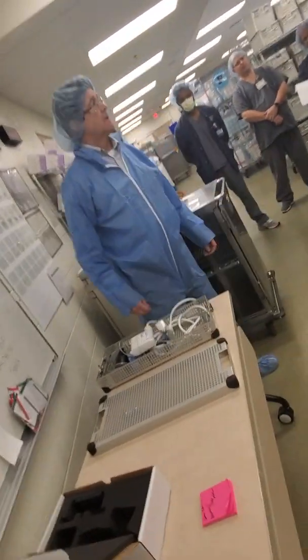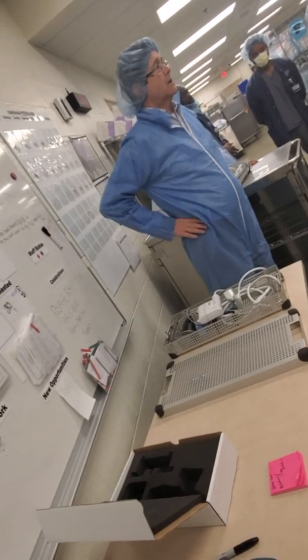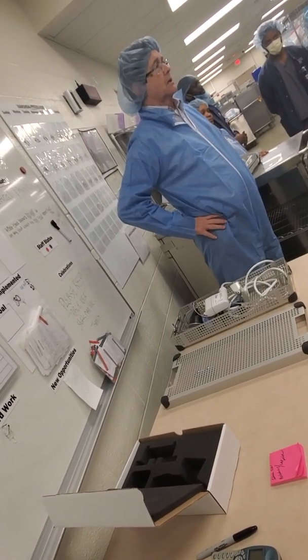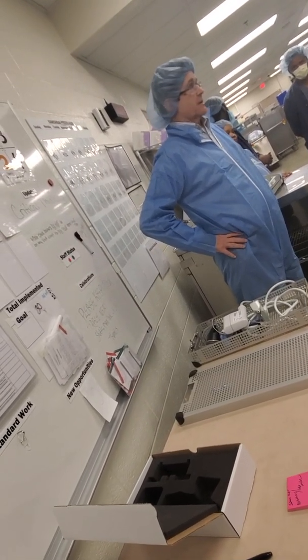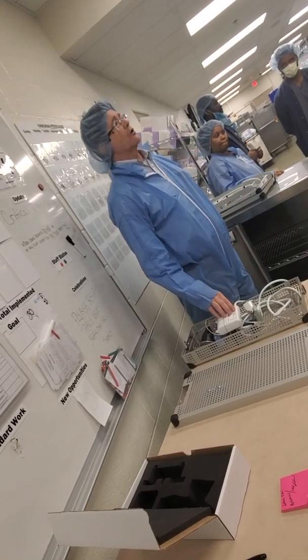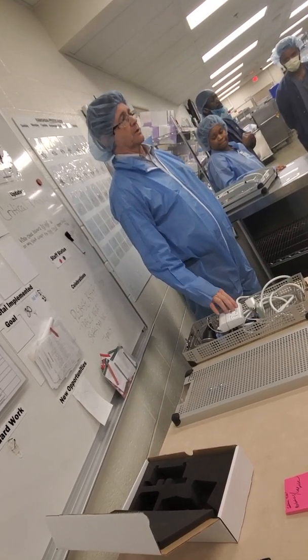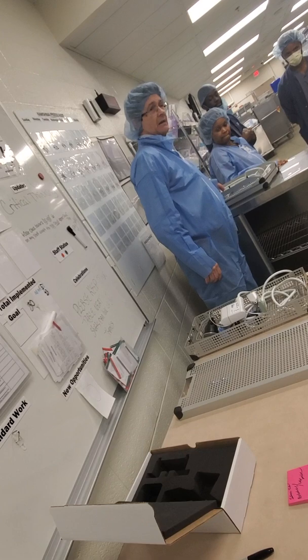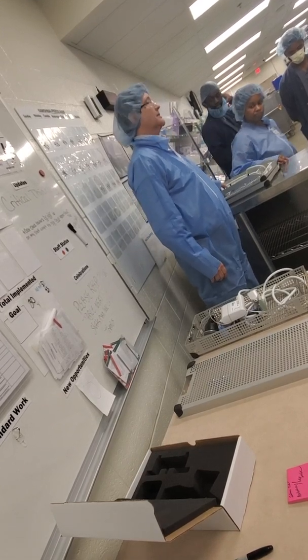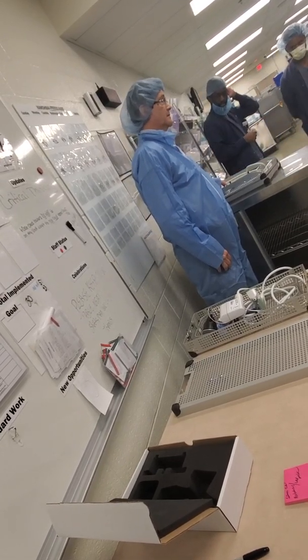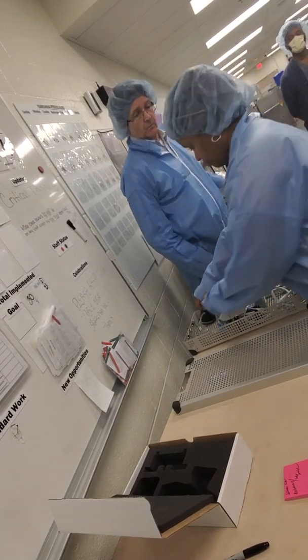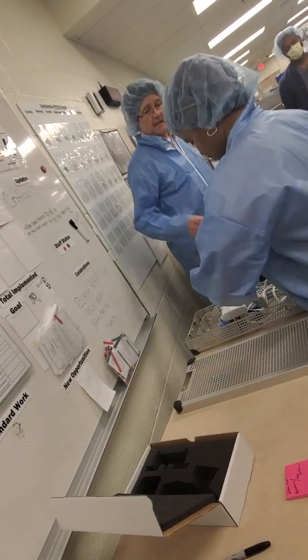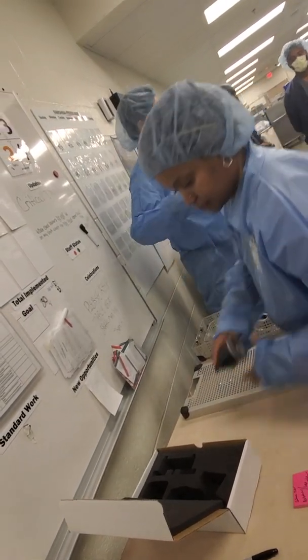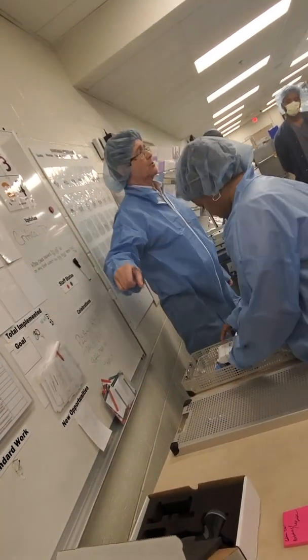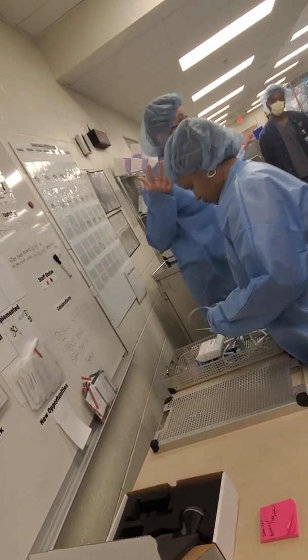So, all of them are tested the same way, the leak test? Yes, because it's the probe. All the probes have the same plug, just like this one. Except you didn't have a leak tester before, correct? We did. You didn't. Well, now you do. It was ordered with the new ultrasound machine. So now you got one.